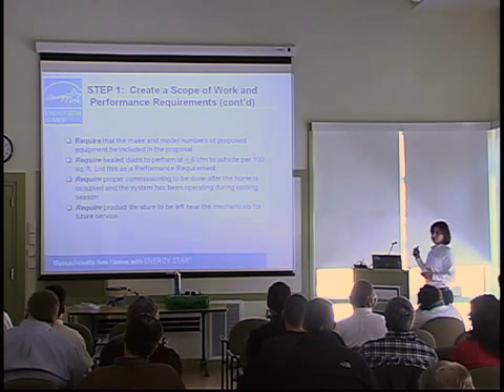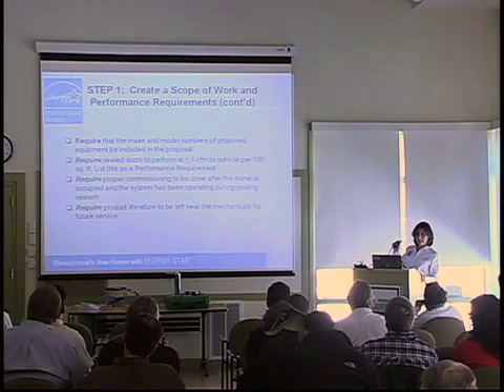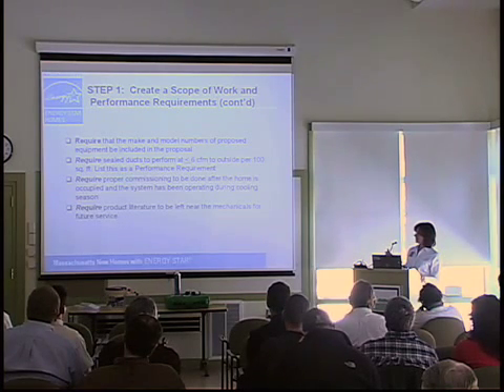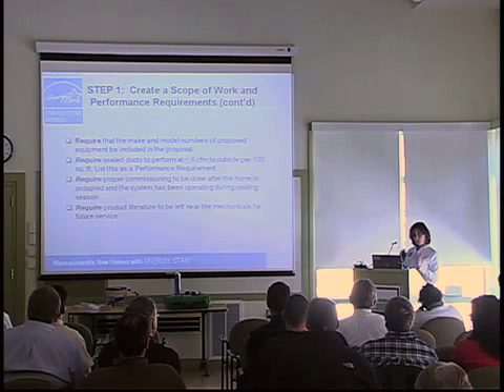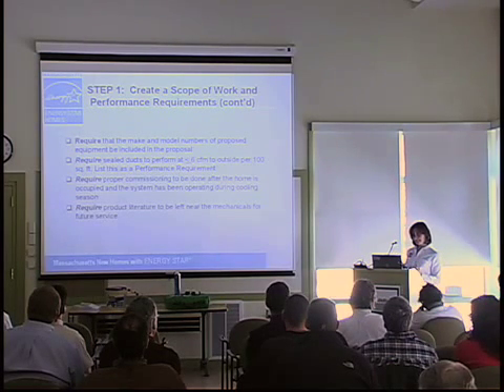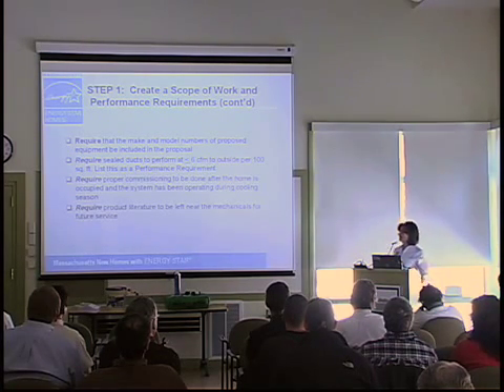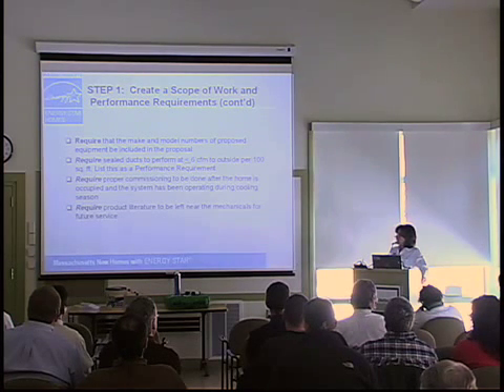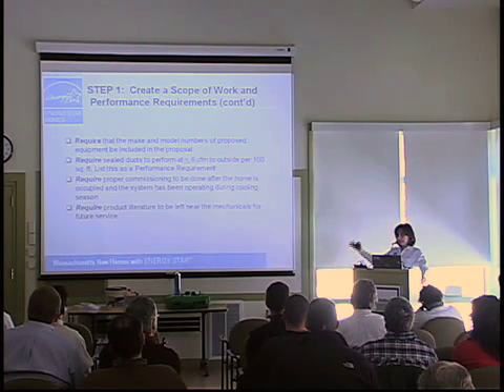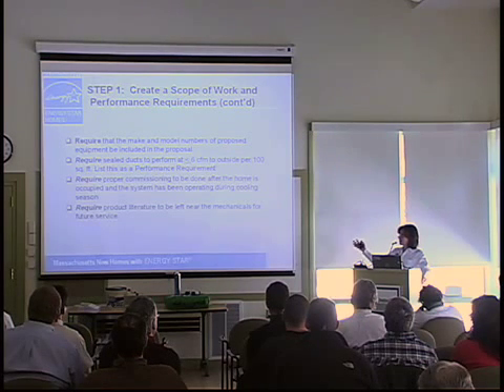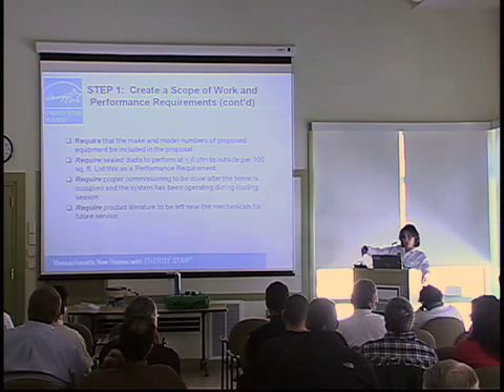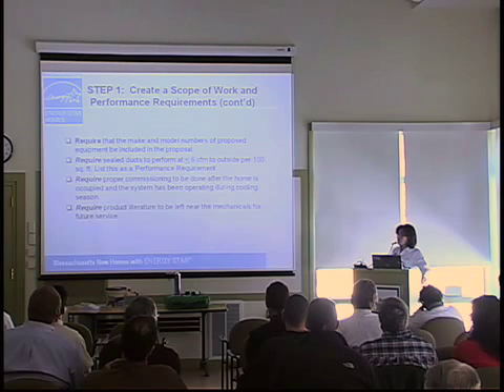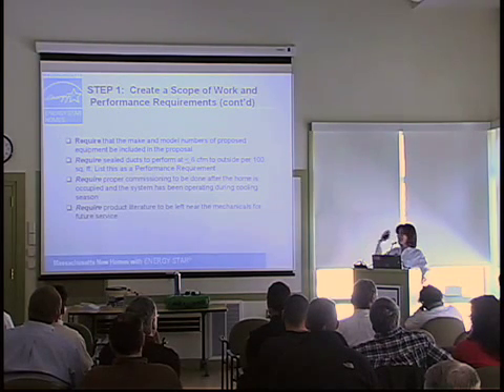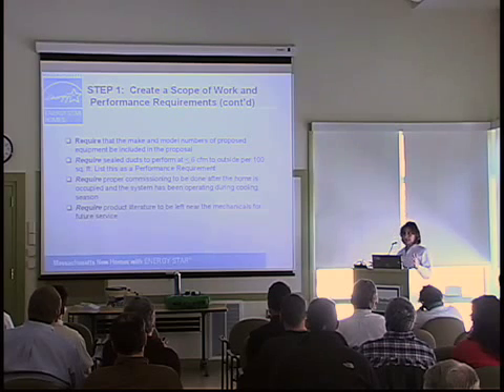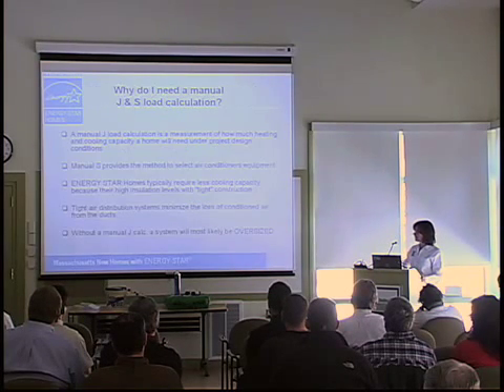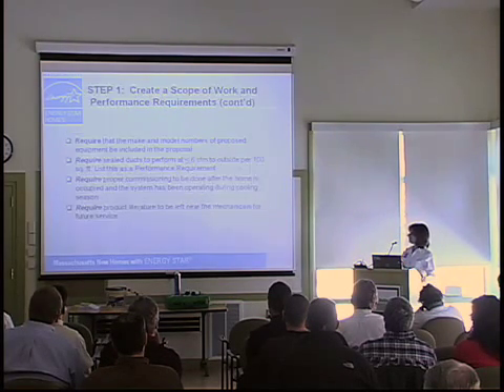There's also a lot of information in model numbers that you'll need to assess whether or not the system has been sized and matched properly in order to achieve the intended efficiency ratings. So, your outside condenser needs to be ARI rated to work with your indoor coil. Those are approved, tested, and verified combinations that enable the system to work the way it's been designed to work.